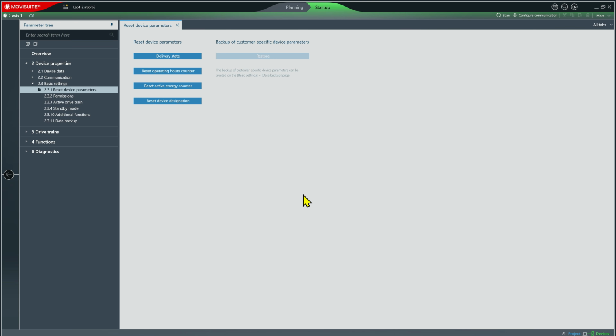I'll click OK. There is only one thing I want to point out. The VFD's name does not get reset when you factory reset it. Notice it's still axis 1. But if you go into the upper corner here, we see a C4, which means the VFD is essentially in a blank condition. So now we're ready to commission it.